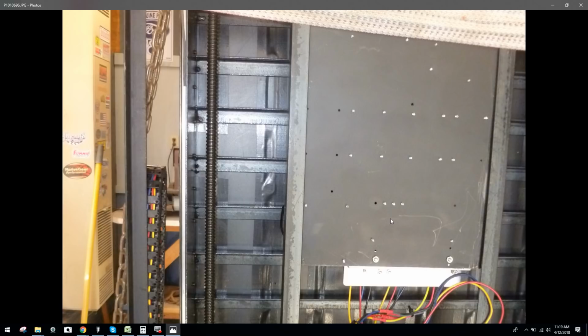If you notice any leads that are not fully inserted in your terminal block, or anything loose, go over the screw set. When you see this base plate mounted to the bottom of the chassis, guys, you have a spindle on top of this chassis that's pulling the most amps. That spindle will generate large amounts of EMI, essentially turning this metal chassis and everything connected that's metal into an antenna, which just translates all that to your wires. They start talking to each other, and you're screwed when it comes to signals.